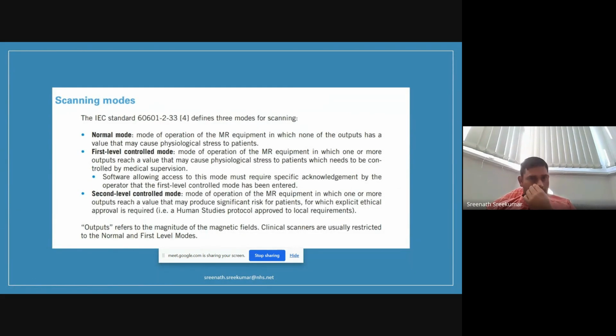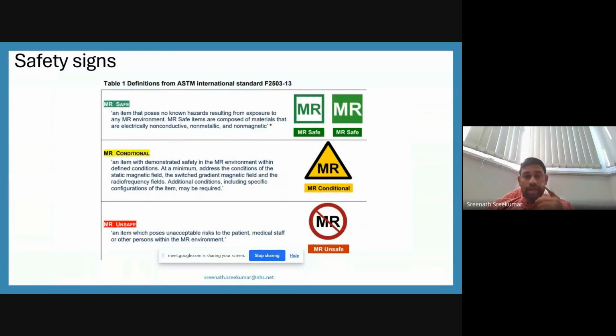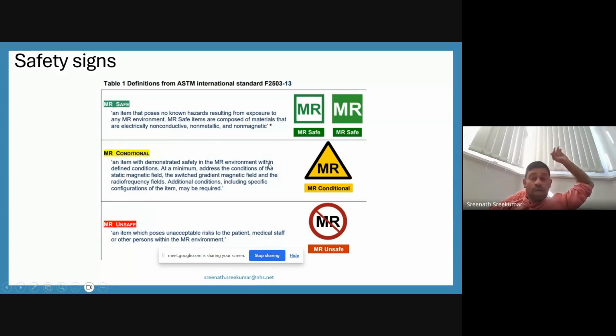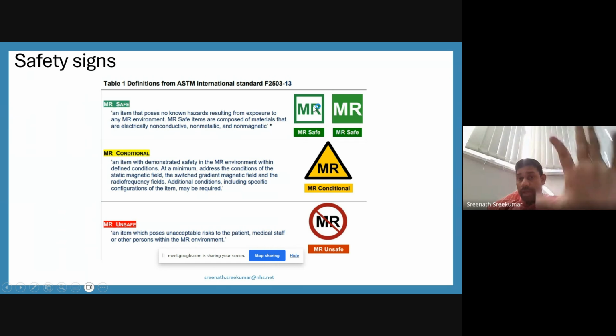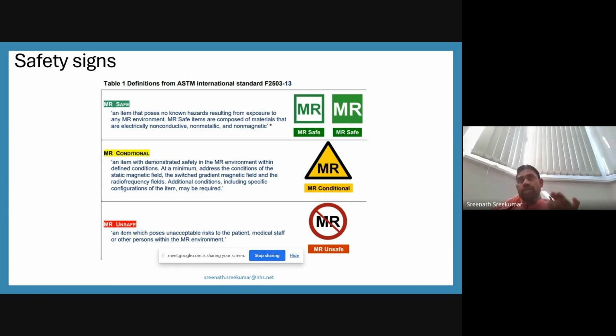The same thing applies: we have to follow normal mode, first level and second level modes, so it's just safe. And for safety signs, you can see safety sign boards now. Easy to understand, the green one is MR Safe. Everything labeled MR Safe is safe to go inside. This does not mean an implant should be inside the patient, but other equipment labeled as safe will be safe inside the scanner, like a wheelchair or trolley. These will have a label and can already enter the room. Otherwise we should not enter.